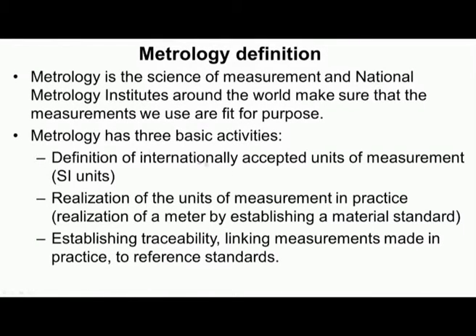Metrology is the science of measurement, and there are national metrology institutes around the world to ensure that measurements are fit for purpose. Metrology has three basic activities: first, defining internationally accepted units of measurement such as length and time; second, realization of units of measurement in practice; and third, establishing traceability — linking measurements made in practice to reference standards — so that instruments are comparable to national and international standards.